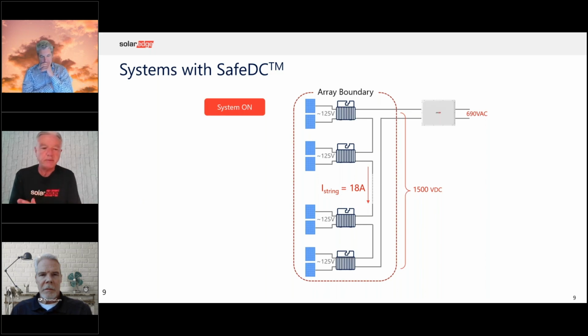And this optimizer also has the safe DC feature. So in a normal string inverter, you can't shut down the array. The only thing you can do is cover it over. That's the way you can shut down a string of modules normally. But when you add the optimizers, you have control now of those modules. And it's not the modules that are wired in series, but rather it's the optimizers. And those optimizers can be controlled. And they control and operate at a fixed input voltage.